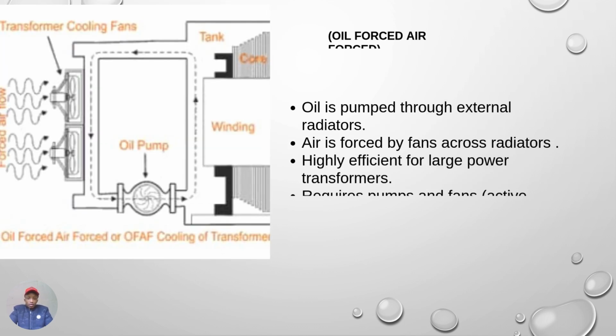Next, we have OFAF. This is an improvement on ONAF because here the oil is also forced - it's pumped through external radiators. Air is forced by fans across the radiators as well. This method is highly efficient for large power transformers, and it requires both pumps and fans for active cooling.